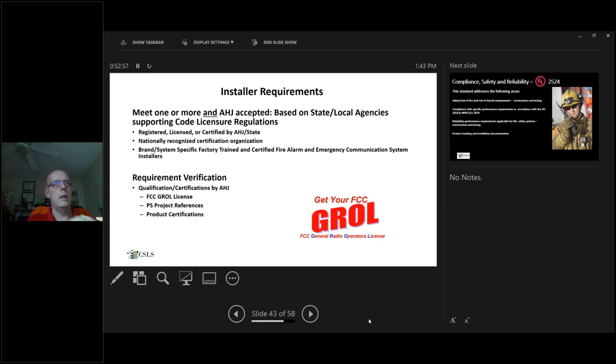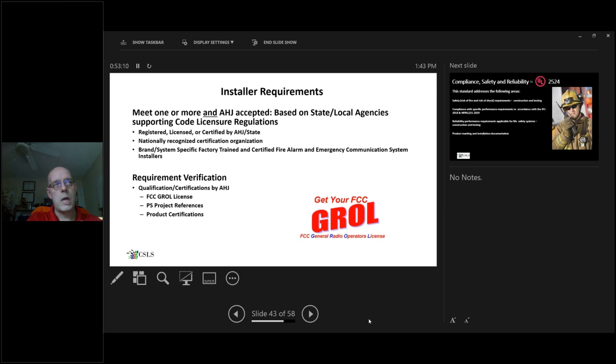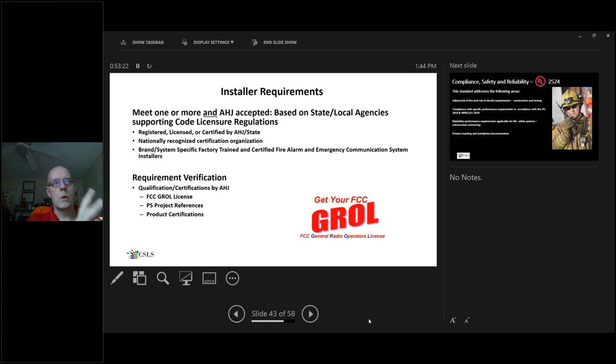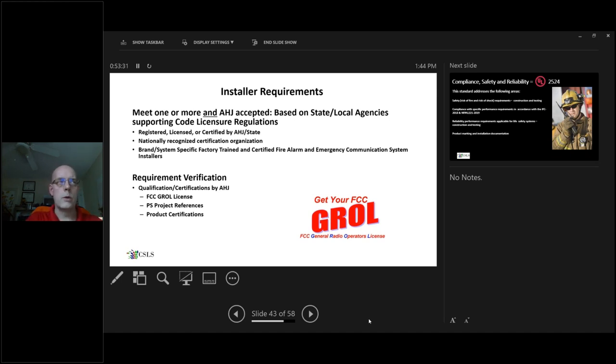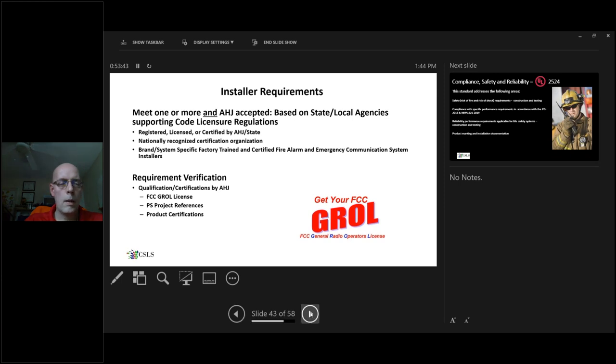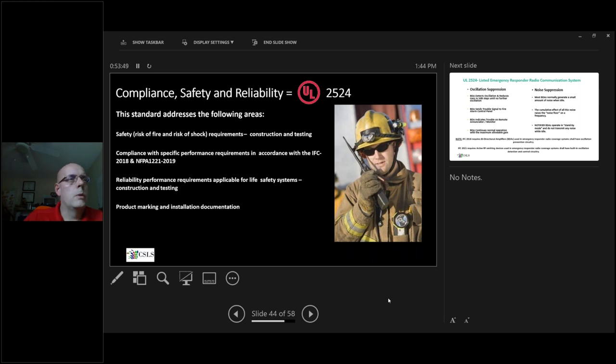The most recent UL 2196, which is pertinent to armor coaxial cable that has a two hour rating, that way you don't necessarily need to have conduit. It's consistently changing. The FCC oversees all this. We're seeing a lot of things change in the industry being adopted to try to ensure there are more and more hurdles for people to attain to justify they're qualified to do installations. FCC was one of the first. There's a GROL license: general radiotelephone operator's license, certification by the manufacturers, things like that. The FCC is also accountable for if we've got a class B signal booster we're installing, then I, as the integrator, the GROL license holder, I need to go to that FCC website and register that signal booster with them. There are a lot of jurisdictions that if it's class B, they then turn around and they will ask me for the signal booster FCC certification information showing that it was in fact registered with the FCC.